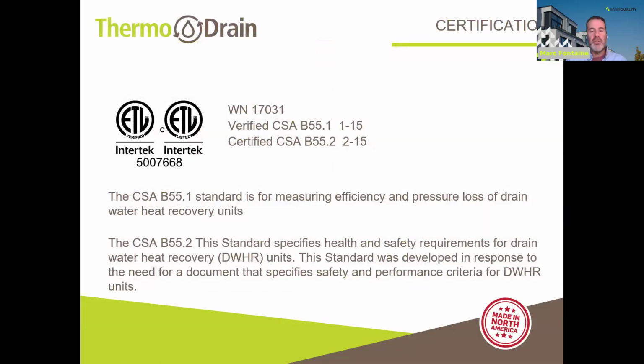As I mentioned earlier, all manufacturers have their products tested by a third party. It could be Intertek or UL or others, against the CSA B55.1 and B55.2 standards. The B55.1 is the performance standard. So we send units out, they're tested by the third party against the standard, the performance is measured, and that's given back to us. Then that's the data that we publish in terms of heat recovery potential. It's the same thing as with heat pumps and windows and other things that are third-party certified.